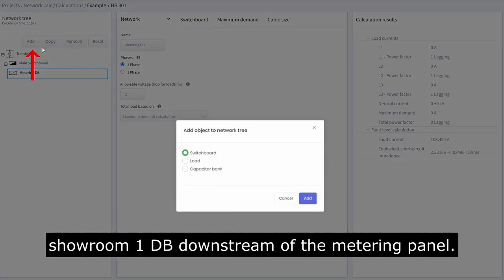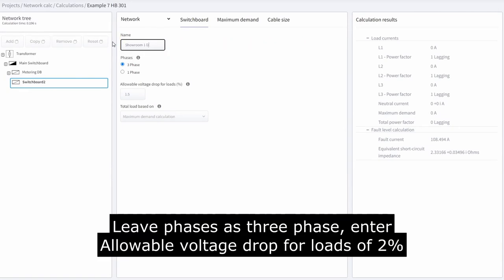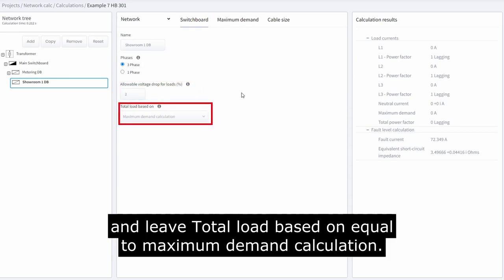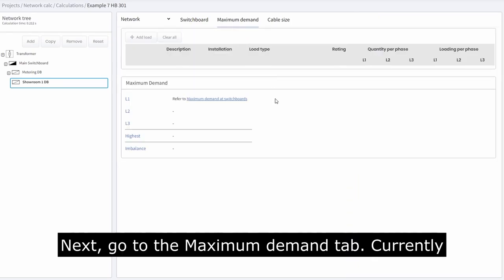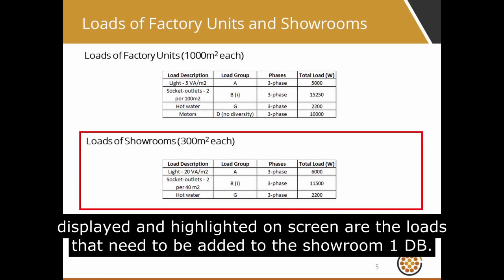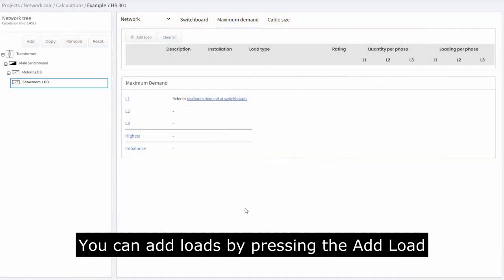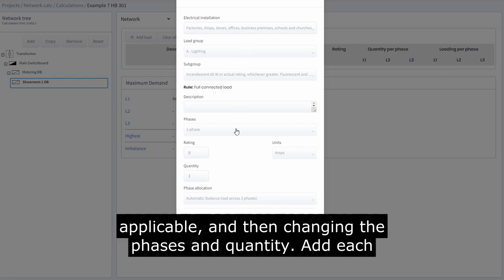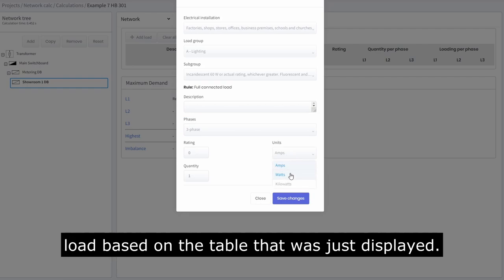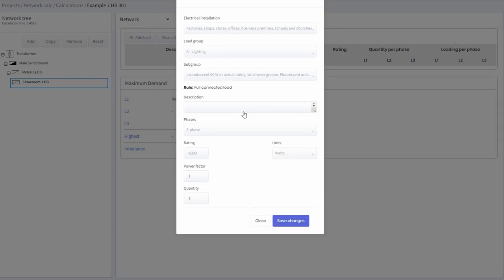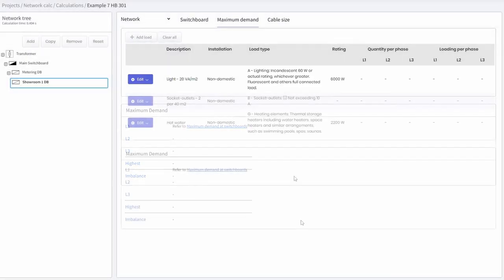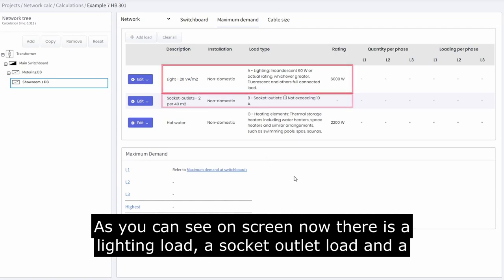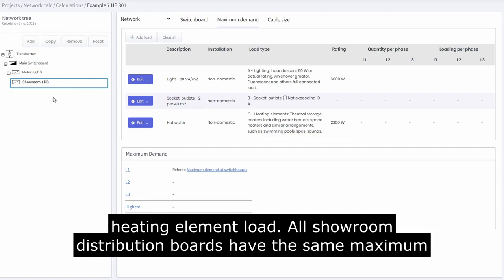Add showroom 1 DB downstream of the metering panel. Leave phases as 3-phase, enter allowable voltage drop for loads as 2%, and leave total load based on equal to maximum demand calculation. Next, go to the maximum demand tab. Add loads by pressing the add load button and selecting the electrical installation, load group, subgroup if applicable, and then changing the phases and quantity. Add each load based on the table displayed. As you can see, there is a lighting load, a socket outlet load, and a heating element load. All showroom distribution boards have the same maximum demand.